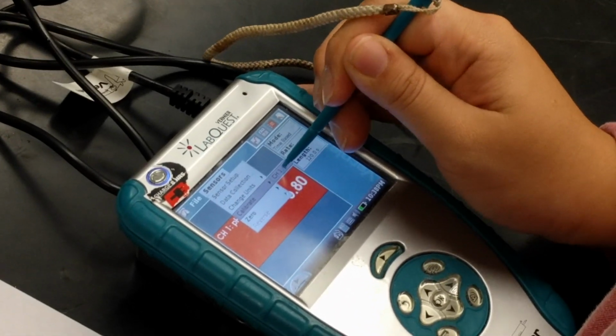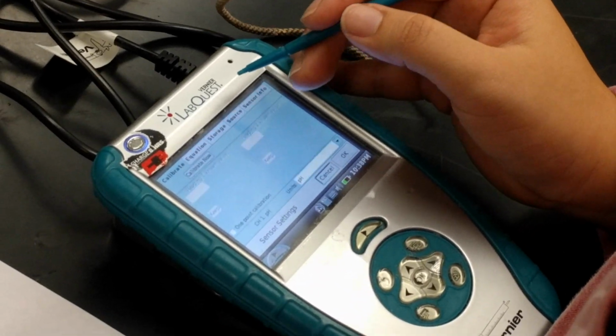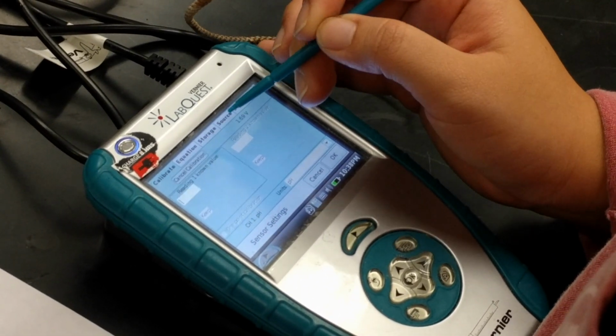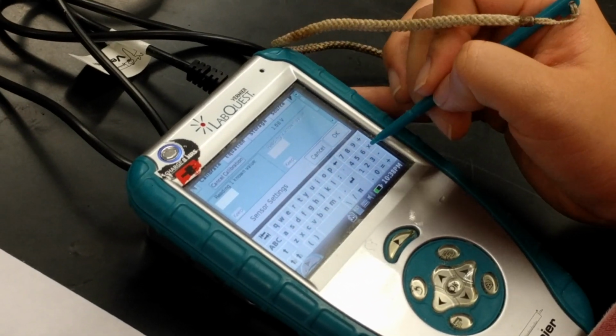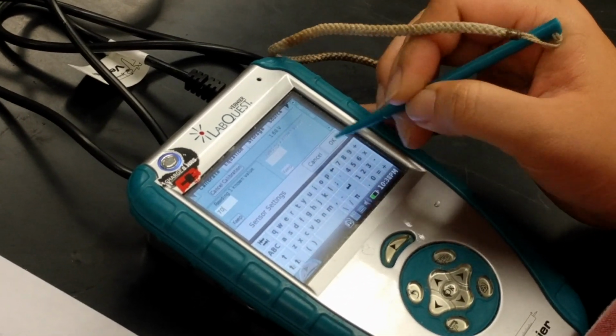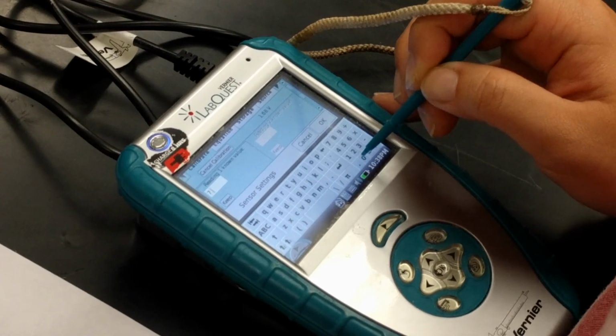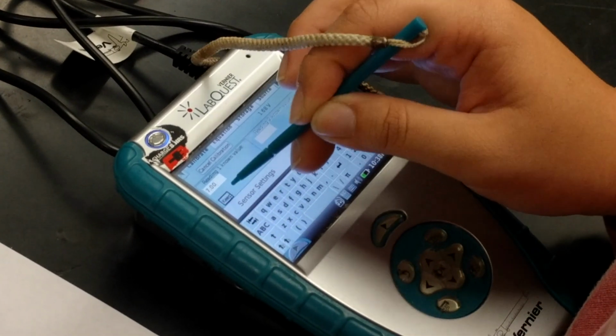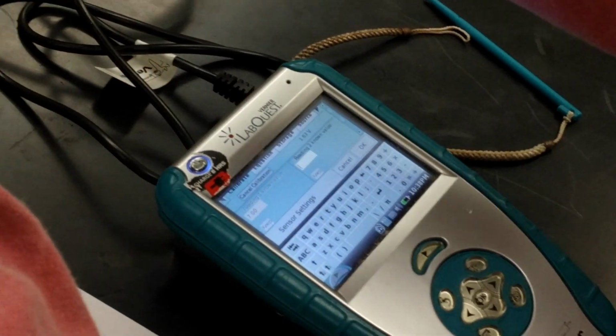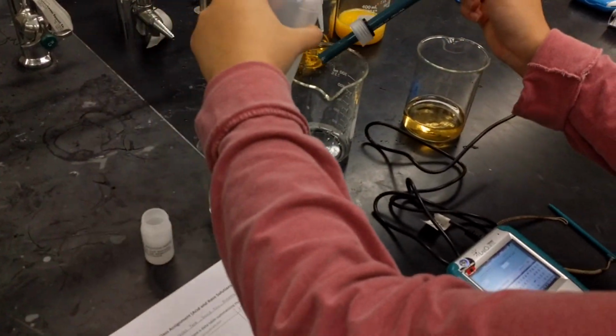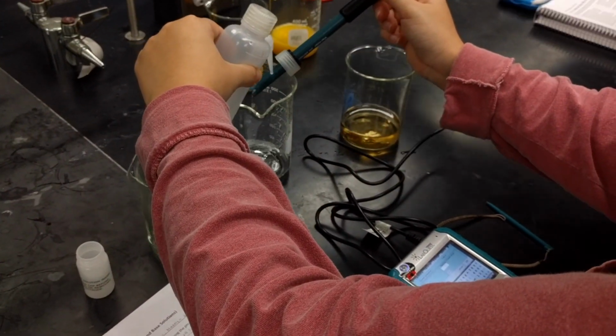Place the probe into the beaker with 7 pH buffer and click Calibrate. You will be doing a two-step calibration, so into the box on the left, put 7.00 and press Keep. Next, wash off the probe with DI water and put it into the 4 pH beaker. Plug 4.00 into the box on the right and push Keep.